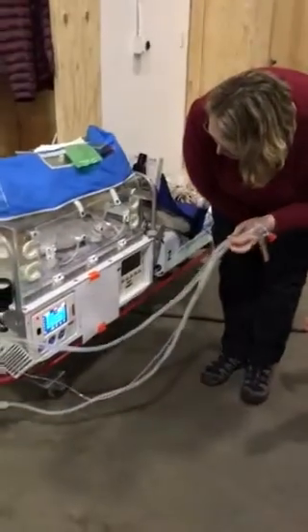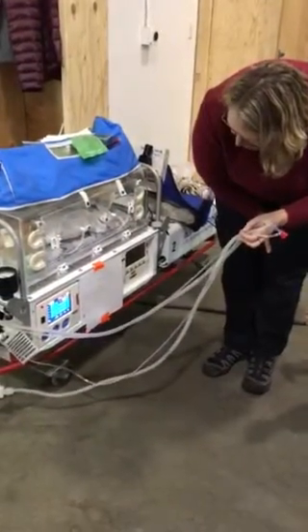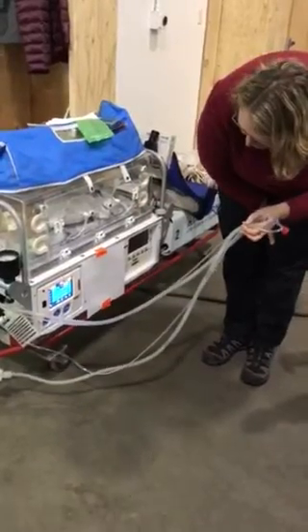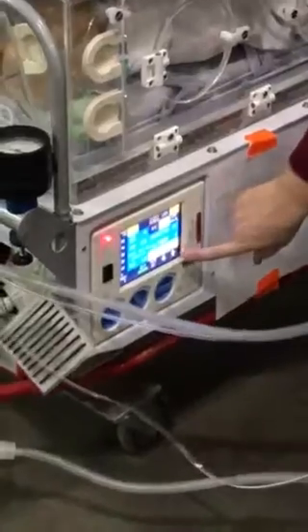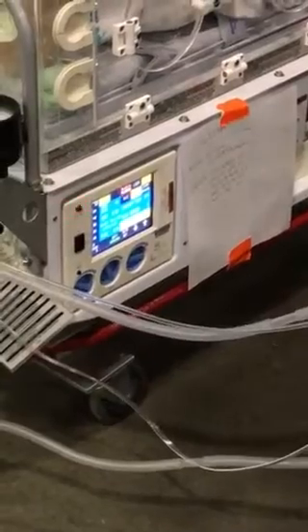All right, and then the pressure support, I usually set it on like 2/3 of my PIP. So if I'm on, or sometimes I'll just set that on 8 or 10. Okay? So this is SIMV, so I didn't have to use a test lung. So I noticed now it's reading high pressure. I was gonna say, I noticed your PIPs are up in the 30s. Yep, and that's just because I changed it over.